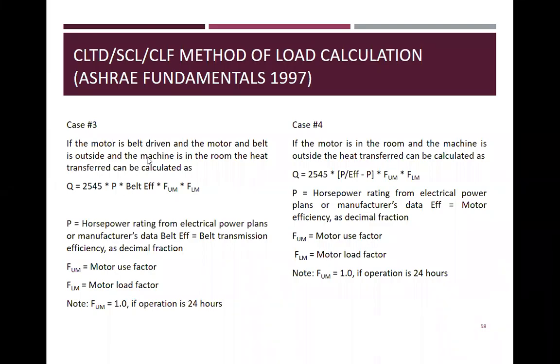So case 3, if the motor is belt driven and the motor and belt are outside and the machine is in the room, the heat transfer can be calculated as Q is equal to 2545 times P times the belt efficiency times FUM times FLM. So yan. So yung P, multiply mo na efficiency, yun na yung sa machine mo, di ba? P is the horsepower rating from electrical power plans or manufacturer's data. Belt Eff is the belt transmission efficiency as a decimal fraction. FUM is the motor use factor. FLM is the motor load factor. FUM is 1.0 if operation is 24 hours.